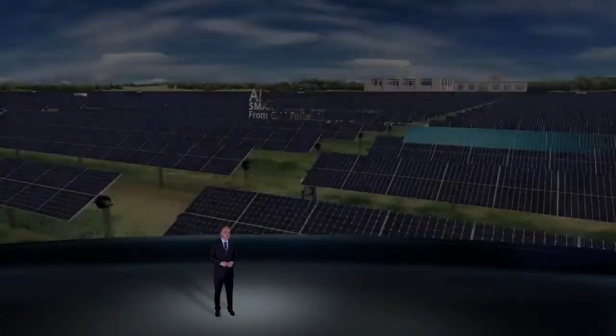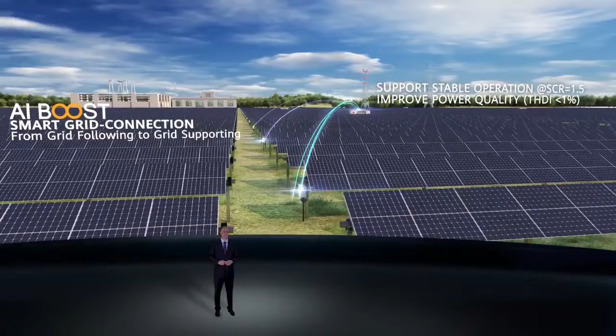In April of this year, a grid fault with a phase-to-phase short circuit occurred and further led to a low voltage condition in this local grid. Both plants managed to stay online and ride through the fault, even in a situation that was far beyond laboratory simulations. So what we learned from this case, for a long-term PV plant operation in a daily changing grid scenario, a grid inverter with a strong grid connection algorithm becomes particularly important.